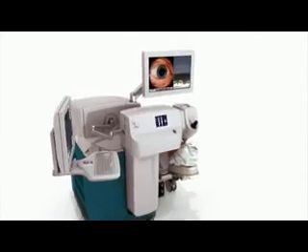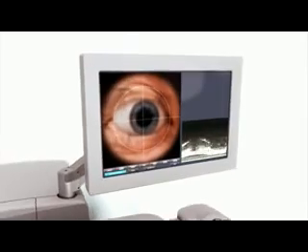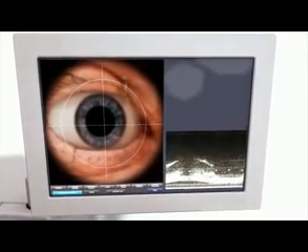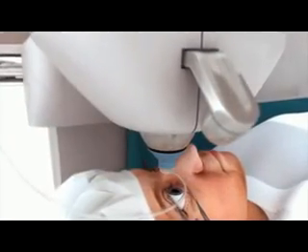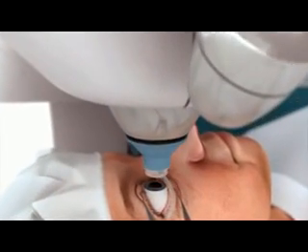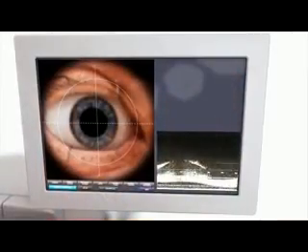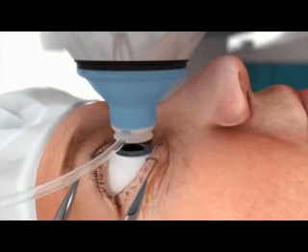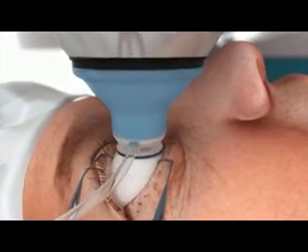The LenSx laser is designed to provide patients with an optimised refractive cataract surgery experience. Featuring real-time imaging and integrated OCT, the LenSx laser allows for visualisation of the entire anterior segment during docking, planning and procedure. The patient relaxes as the surgeon utilises the high-resolution video microscope and live OCT image to gently guide and dock the disposable patient interface to the corneal surface.